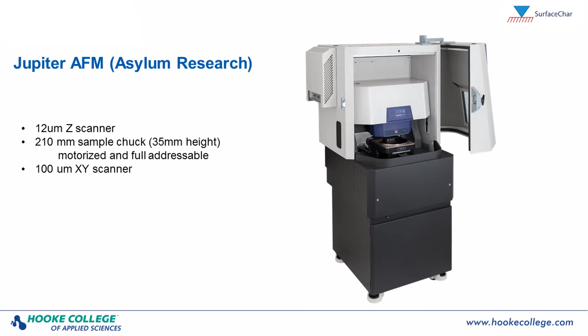Here's our large sample component, the chuck, this large circular portion here. It's a 210 millimeter sample chuck, and it can accommodate samples up to 35 millimeters in height, so a lot of flexibility there. The sample chuck is motorized and fully addressable. And the XY scanner is a classic 100 micron range in X and Y, classic for most of these large sample instruments. It combines a couple of key and very helpful features.